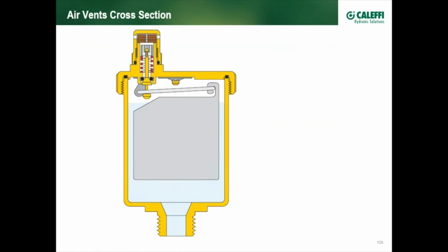It's important to know, whether Caleffi or Spirotherm or Taco or Bell & Gossett, there's a couple of key specs to keep in mind, and that is the operating pressure rating of the vent, sometimes called the maximum venting pressure. It might be 60 PSI, 90 PSI, 30 PSI, depending on the make and also on the model. What is the venting pressure?